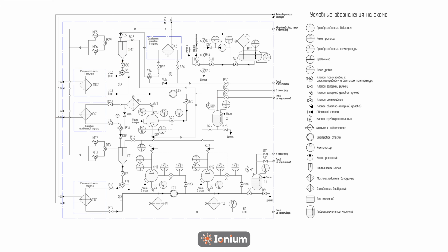The compressed helium, with a temperature of about 98 degrees Celsius and a pressure of 24 bar absolute, goes into the oil separator, OM2, where it is effectively separated from the oil. Oil is directed from the separator to the water-oil heat exchanger, MO2, where it's cooled to approximately 28 degrees Celsius, and then injected into the machine's working chamber at approximately 16.8 bar absolute pressure.